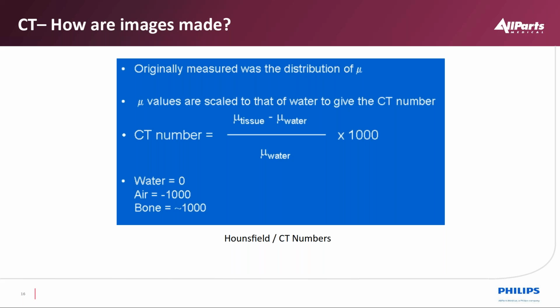So what we do is we scan water, we scan other materials before we scan a patient, and we create basically a calibration file. Each detector element, the crystal, the A to D circuit that converts it, and the amount of coefficient coming out, not off a straight shot through the image, but maybe through the angle of the X-ray beam as it travels, will be compensated for by those calibration files. So at the end of the day, water will be 0 on the scaling system, but this is not tap water at your house. This is distilled deionized water as a standard. So one of the things that we can do as a quick check is take a gallon of distilled deionized water, put it on the scanner, and scan it to see if water is 0 plus or minus spec.